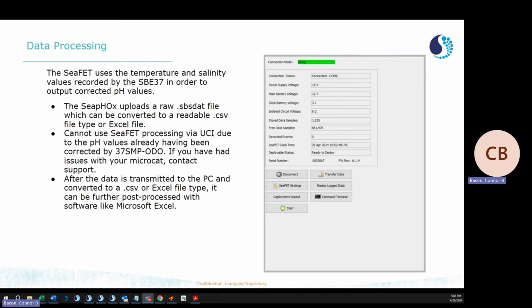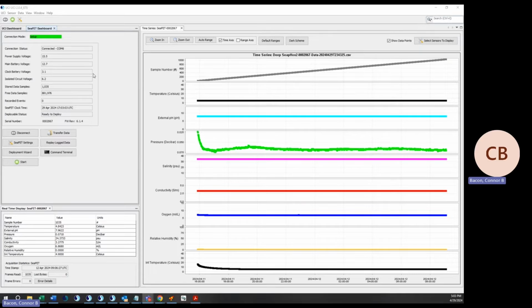The SeapHOx system uses the salinity and temperature values recorded by the 37 SMP in order to output corrected pH values. These values are contained in an SBS DAT file, which can be visualized in UCI as seen earlier using the transfer data function. You cannot use the SeaFET processing tab in UCI with the SeapHOx's data, as that is primarily meant for salinity correction, which is done automatically by the SeapHOx. If you do run into issues during deployment with your microcat, we recommend that you reach out to support directly to discuss your options. Once you've finished transferring your data, go to Data and Export Log Data.